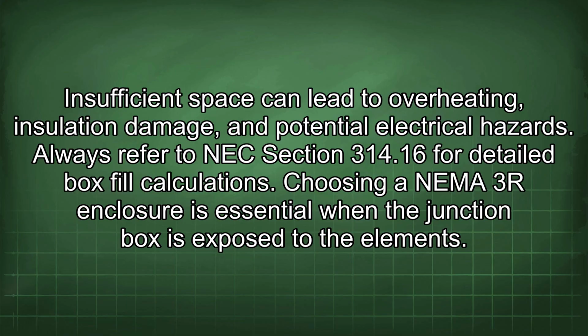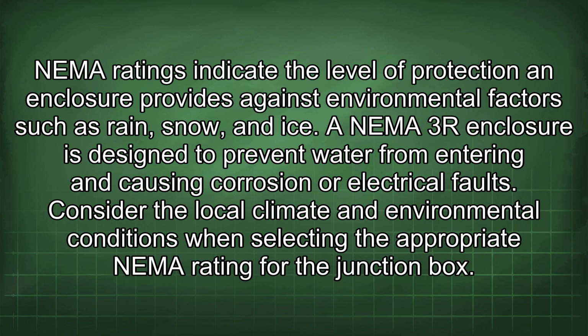Choosing a NEMA 3R enclosure is essential when the junction box is exposed to the elements. NEMA ratings indicate the level of protection an enclosure provides against environmental factors such as rain, snow, and ice. A NEMA 3R enclosure is designed to prevent water from entering and causing corrosion or electrical faults. Consider the local climate and environmental conditions when selecting the appropriate NEMA rating for the junction box.